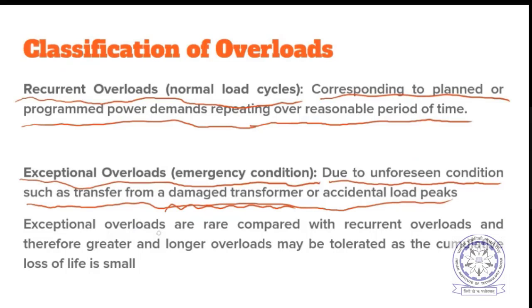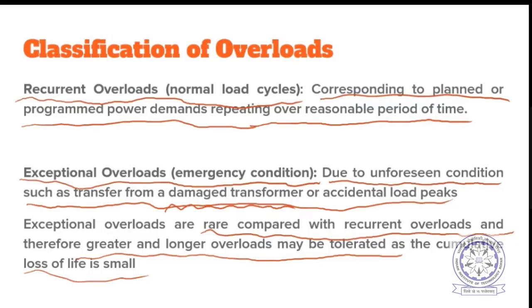So exceptional overloads are rare compared with the recurrent overloads, because recurrent overloads are planned and every day they may occur. But exceptional means, as the name itself defines, an exceptional condition or emergency condition. Therefore, greater and longer overloads may be tolerated under exceptional conditions, as the cumulative loss of life is small, because that will not continue forever. If you are overloading continuously every day for 2 hours, it will have more impact than an emergency that occurs once in a year or once in a few years.